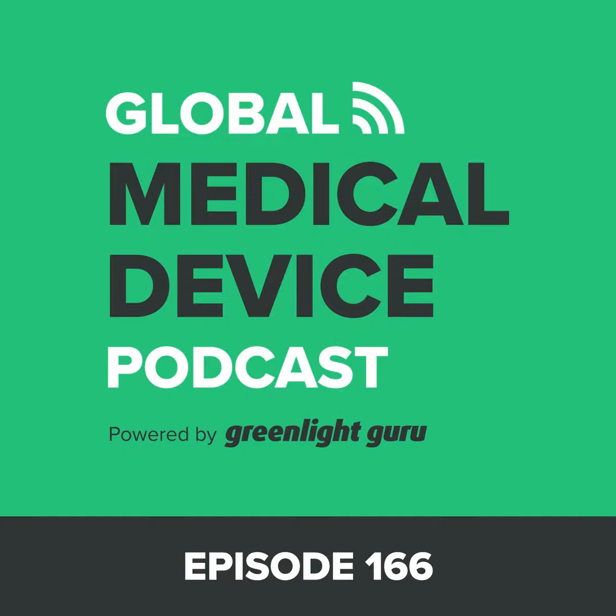And again, I'll give you an example from my world, John. I had a company come to me some time ago. They said, we're using this particular material. It has a history of use in other medical devices in the body. And I said, okay, fine. Tell me more. It turned out that they were doing a blood contact application, and they were trying to make comparisons to similar materials that are put in the abdominal cavity. In other words, in contact with the visceral organs.